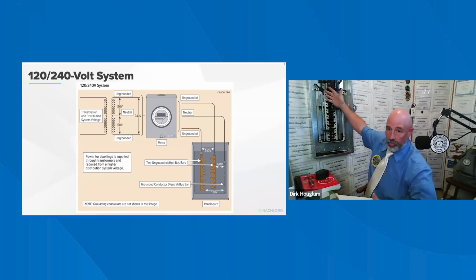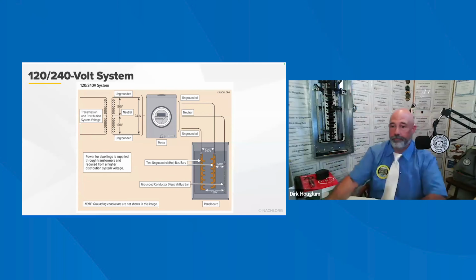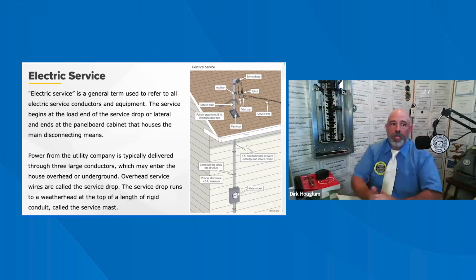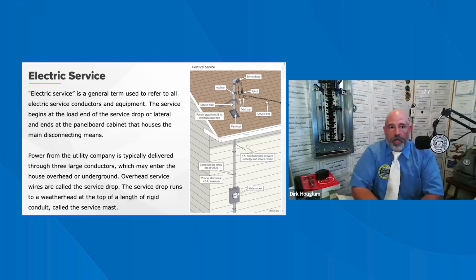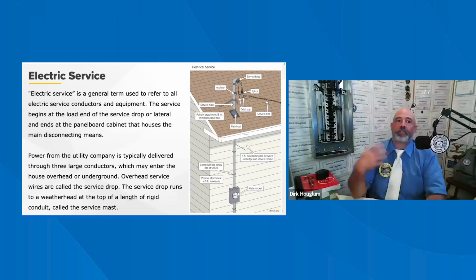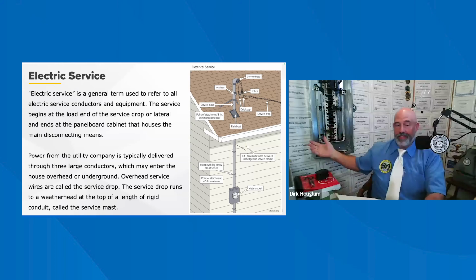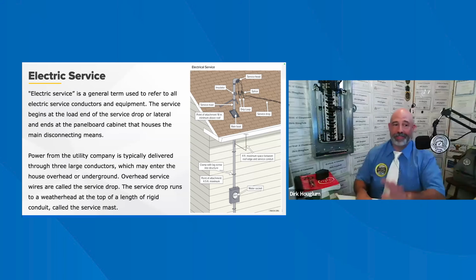120 equals 240. So got it? That's how that actually works. So service, the electrical service, is the general term used to refer to all service conductors and equipment. The service begins at the load of the service drops, the lateral, and ends in a panel board cabinet that houses the main disconnect means. So that's basically what that is.